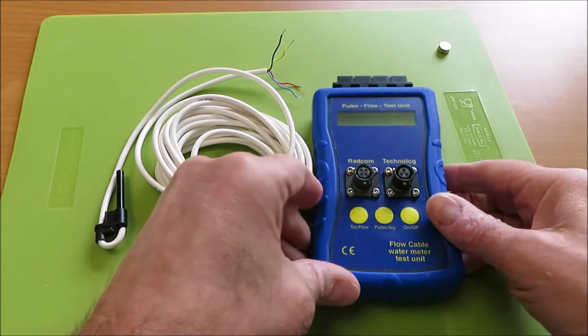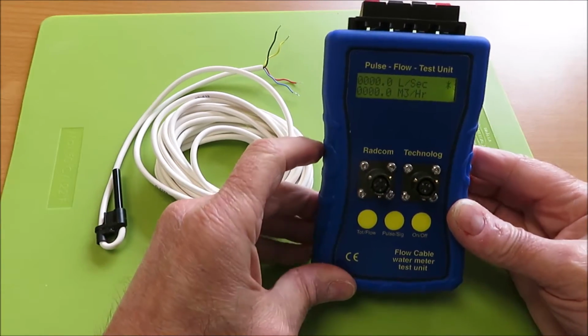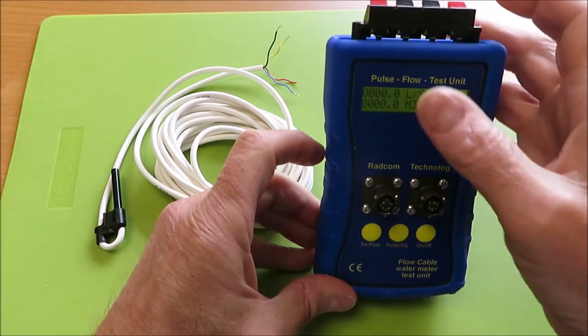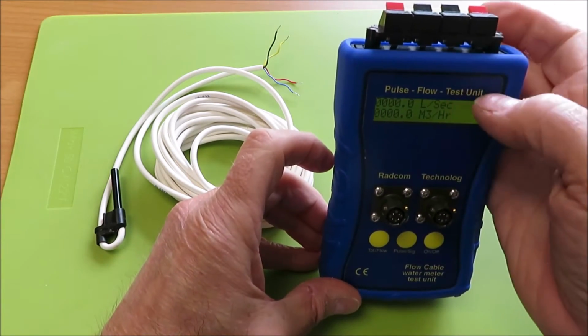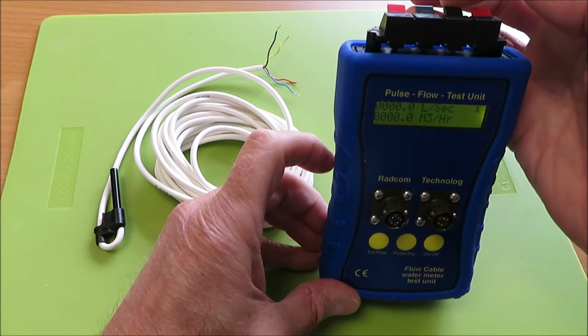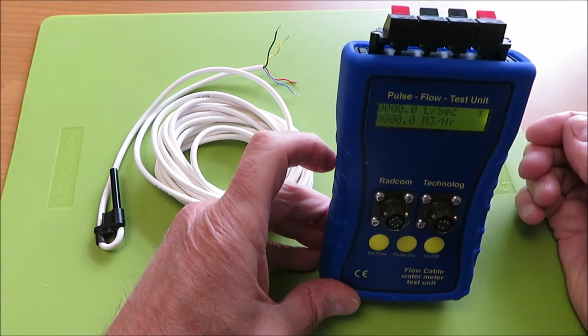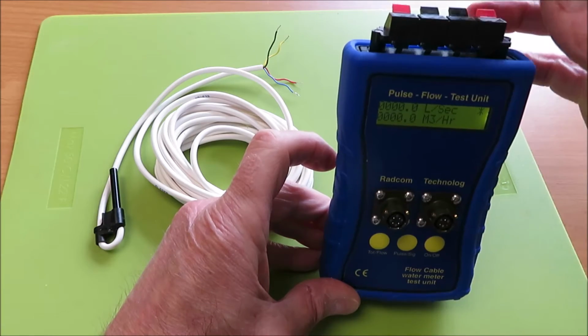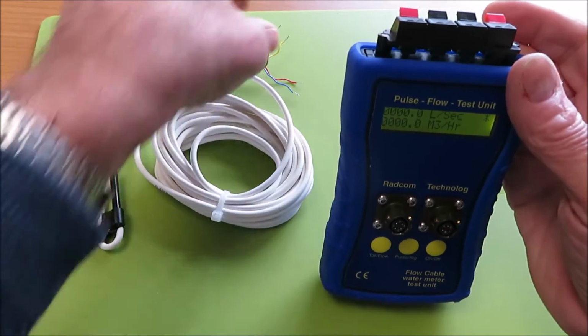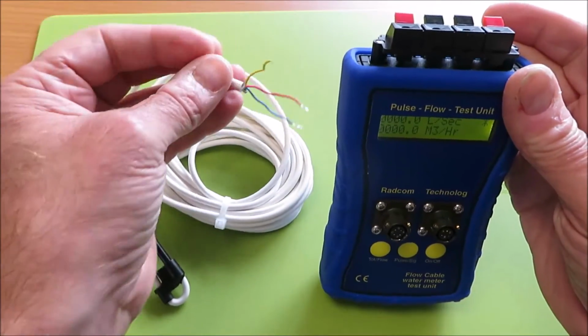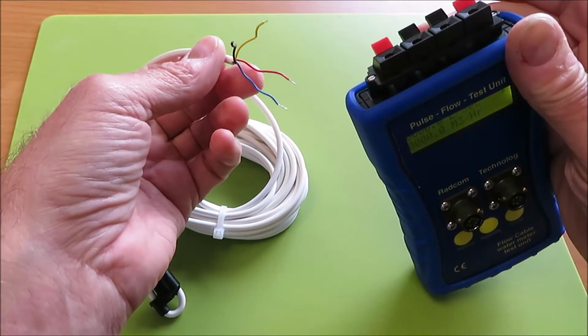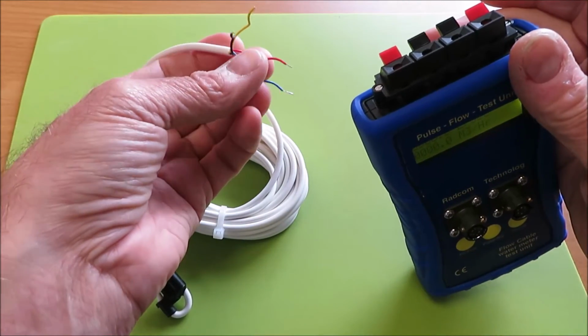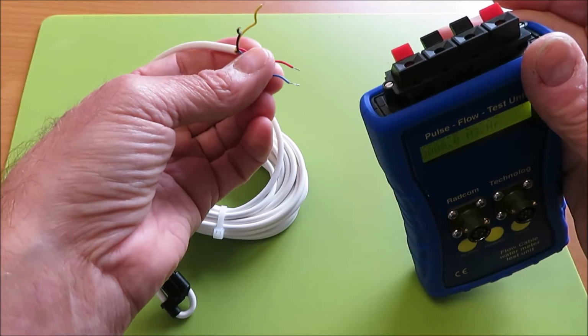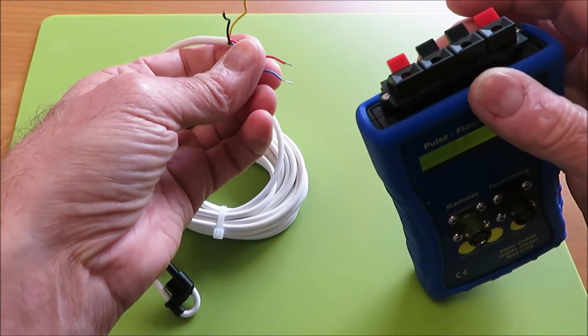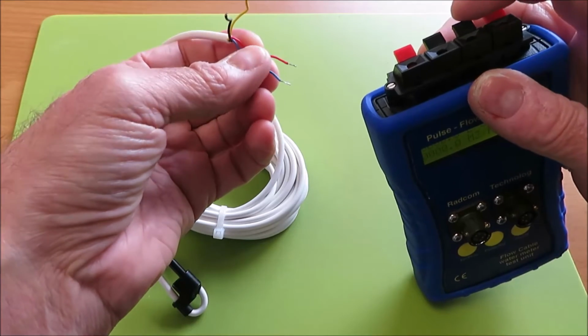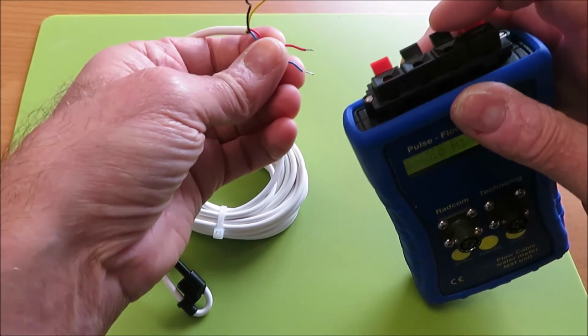So firstly, I've switched the unit on, as you can see there, and I'm going to use the test unit side with the negative or black and red positive inputs for the flow sensor. So taking the bare wires, as I said earlier, I do know that it's the blue and red, and on this particular sensor it doesn't matter which way round they are. It isn't polarity sensitive because it is merely just a switch closure that we're looking for.